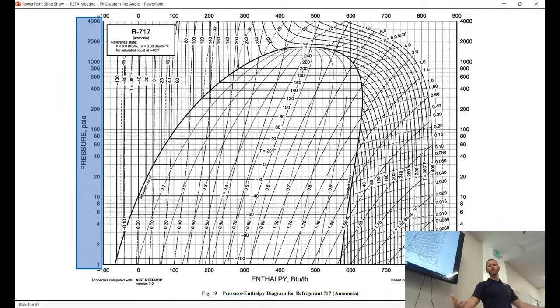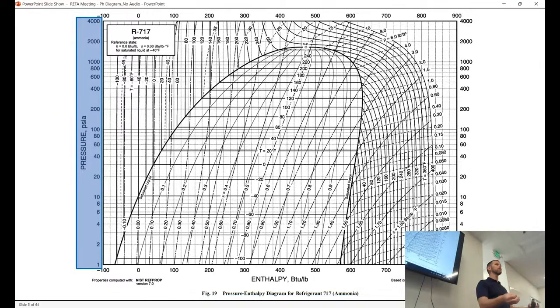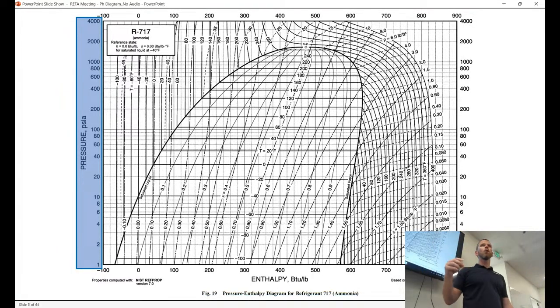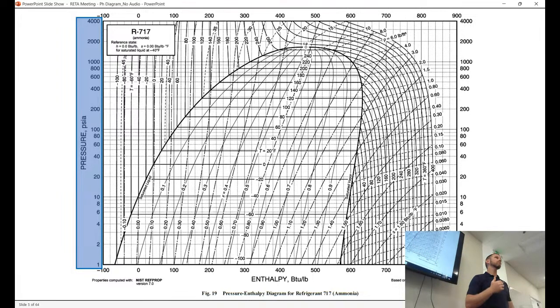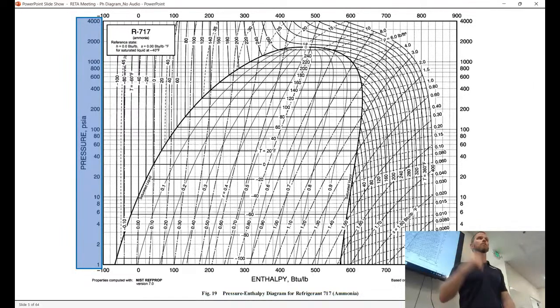What is absolute pressure? It's gauge plus 14.7 — at sea level, taking into account the pressure on our atmosphere. In terms of engineering calculations, you do have to use absolutes. If you're charting a system and you try to mimic what I'm about to do but you do it off gauge pressure and put in absolute, your results will be all fouled up. So you've got to add 14.7. Another thing that's really important to note: notice the difference between 1 PSIA and 10, and now from 10 to 100 is the same distance. This is a logarithmic scale — every equally spaced increment is 10 times bigger than the previous one. That's what a log scale is.